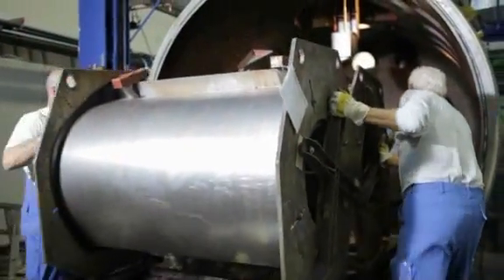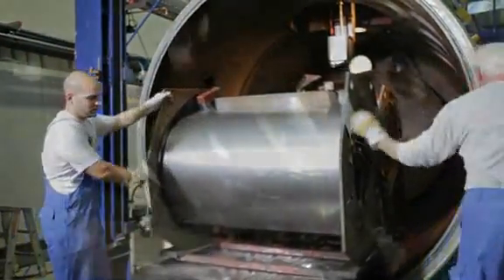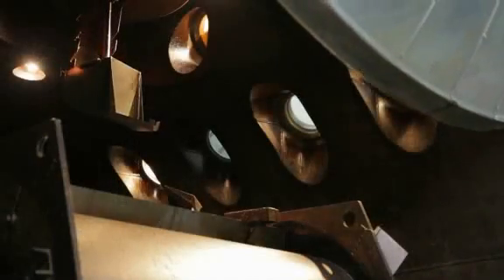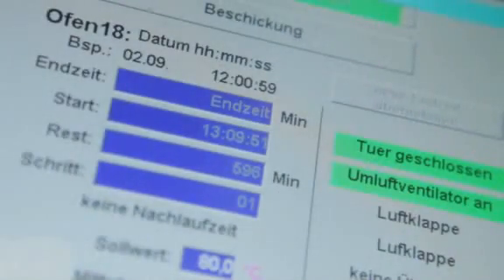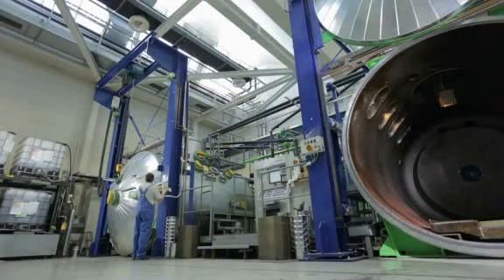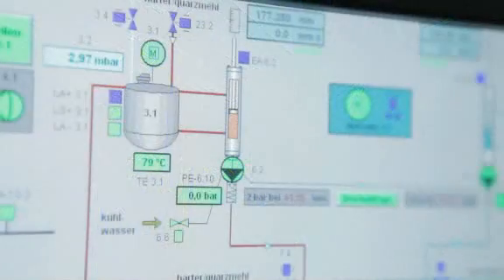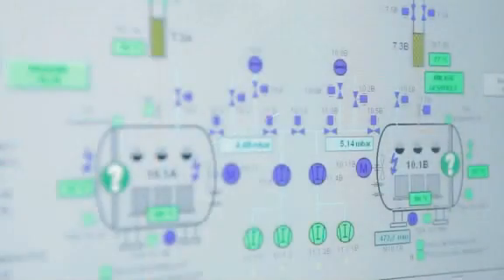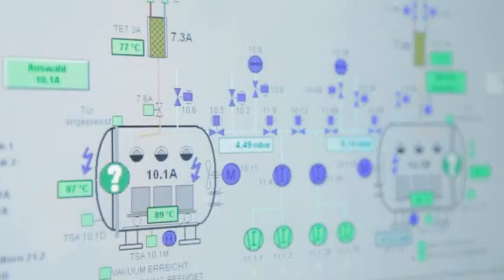The real secret of the Geafol technology lies in how it is made. Together with a cast resin, the coils are cast into a solid block in a vacuum furnace. Because aluminium and cast resin expand at a similar rate when exposed to heat, the mechanical stress remains minimal, even when exposed to extreme changes in temperature.